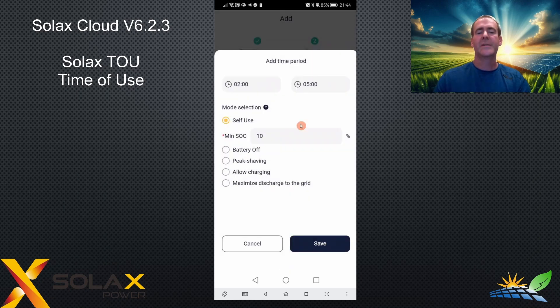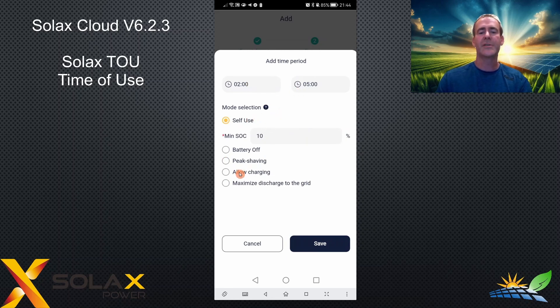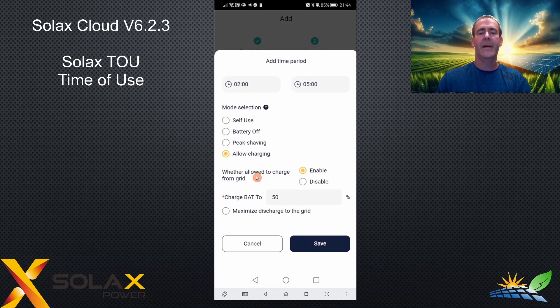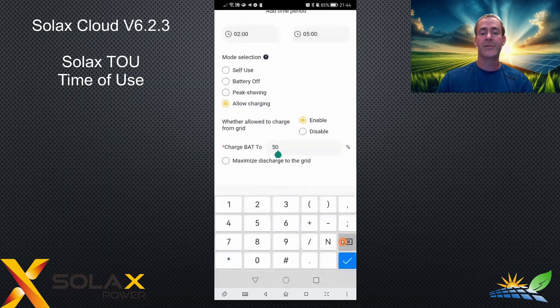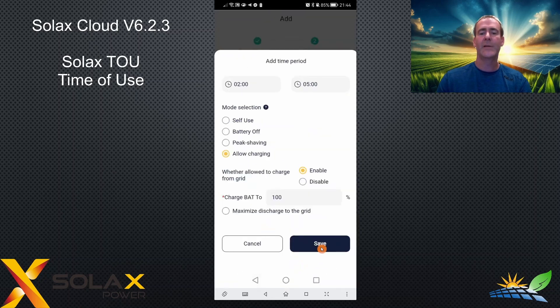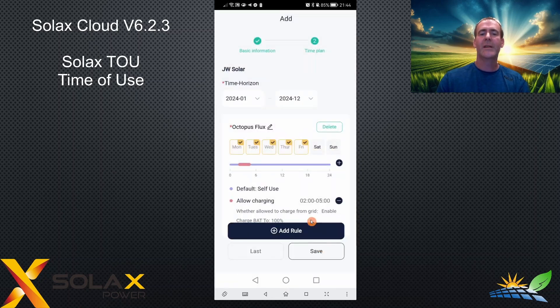When I've set the times, I'd like the battery to charge between those two times, so I'm going to click allow charging. Then you need to select whether you want to charge from the grid — which I do — and which percentage to charge to. I'm going to say charge to 100%. Click save. You can see it's colored a pink line between two and five o'clock, and it's added the TOU charging time two to five.